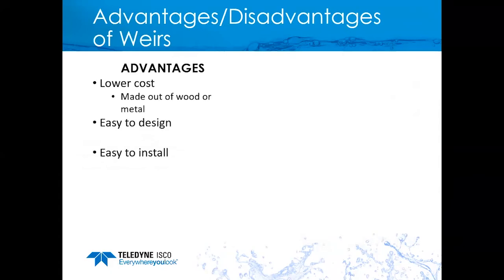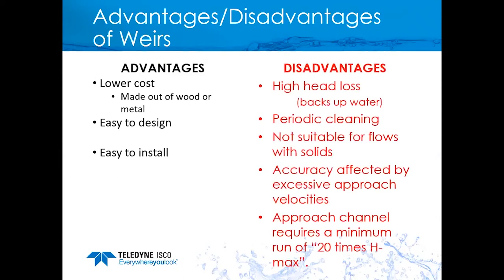Advantages of a weir: low cost — especially if made from wood or metal — and a simple design, easy to design and install. Disadvantages include higher head loss because we're putting a wall across the flow stream, which backs up flow. It can require periodic cleaning and is not suitable for flows with solids. Accuracy is affected by excess approach velocity — do not use where fast-moving velocity approaches the weir. The approach channel should be a minimum of 20 times the maximum head height, requiring a good straight run of channel before the weir.